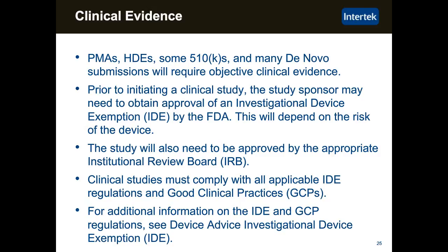In the case where a device is significant risk, the sponsor needs to register with the FDA and file for that investigational device exemption. In the case of a non-significant risk device, they can conduct a clinical study by getting the approval of the Institutional Review Board. All clinical studies must comply with the IDE regulations and must comply with good clinical practices. And there are recent guidances from the FDA as well as ISO standards that are accepted worldwide on how to conduct good clinical studies. Once again, additional information is available on the FDA website, and if you see their device advice under investigational device exemption, you'll have plenty of reading material available to you.